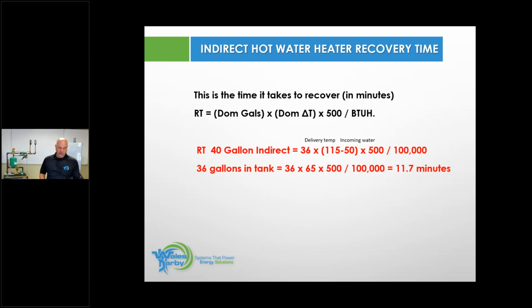So what does this formula look like here? It's 36, that is the volume of water in my indirect. 65 is the difference from my water entering the home, going into my indirect on the cold side. 115 is the target temperature I want going out to my hot water faucets. So the difference between 50 and 115 is 65. So 65, and then we got 500.